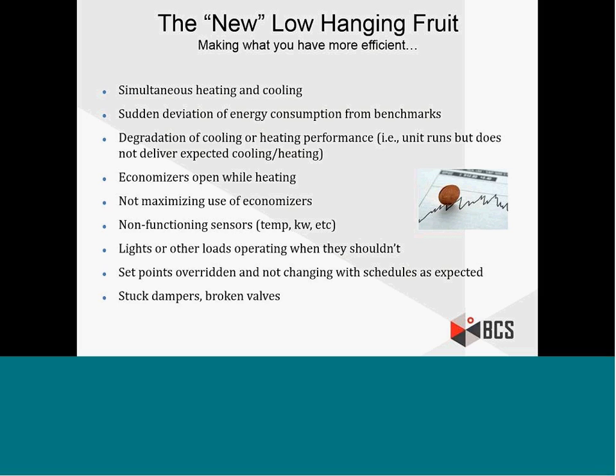Others you'll see here are equipment just not operating properly. Maybe it needs calibrated, or maybe it needs repair. Maybe it's just not being used. We have a number of clients with variable frequency drives on their equipment, and they're just using them for soft starts. We go out and take more control, and really they're doing that because they don't have the information — they don't know what it should actually be running at. So we go take control of those. It's a great, small controls upgrade, a quick sequence into the system, and you're getting some great savings off your equipment out there.